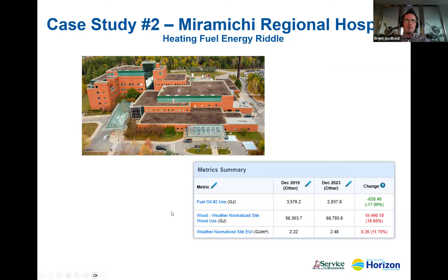So here's the CUSUM, or cumulative sum again. We have a baseline that's quite a bit older this time, 2013 to 2014 was our baseline period. We did some major work with the actual wood boiler at that time, and also did steam trap surveys, fixed a bunch of steam traps. So we started saving energy, kept saving it all the way up till about November of 2020, and that's when you can see our energy leveled off. At this time frame, about 3 years, we were using the same amount of energy as our baseline period back in 2013-14, which isn't what we wanted.